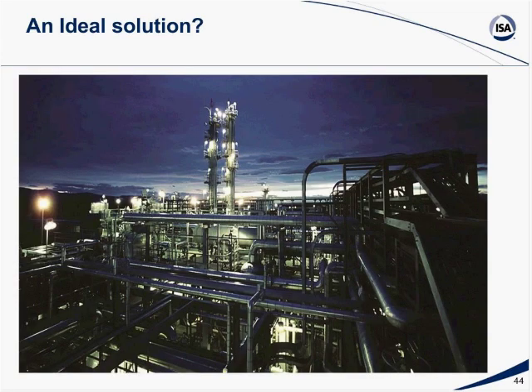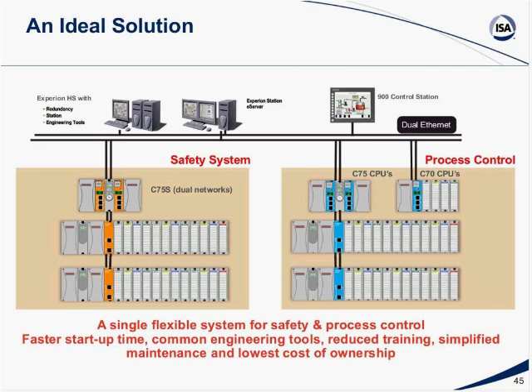So let's now take a look at an ideal solution that can help with some of these choices you would have to consider before selecting a process and safety system or a burner management system. What you're looking at here is an HC 900 process and safety system. This architecture provides a snapshot of two separate systems, a safety system on the left and a process control system on the same network, but they are segregated as two separate systems. This is the best part of the HC 900 system: it can be used as a process control system and also a safety system.